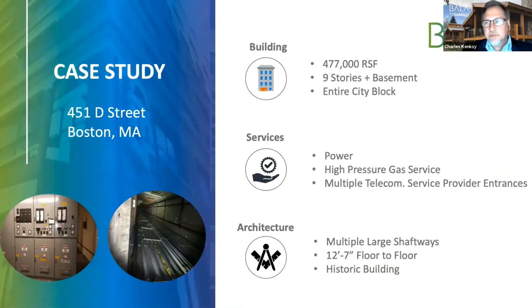It used to be a telecom service provider, so it had a lot of power and even high-pressure gas, which is unusual. The service was 13.8 kV, with three 4,000 amp, 480 volt double-ended switchboards and over 40 watts per square foot of power, so it fell well within the metrics Scott showed you. We added two 300-ton gas-fired DX-cooled rooftop units to support the labs with makeup air, and there's a strobic array on the roof for the exhaust. We use strobic-type fans, though there are other similar manufacturers, which induce air from outside the building to give us a larger air quantity and higher plume, so we get the velocity we need and get it up and away from the building.